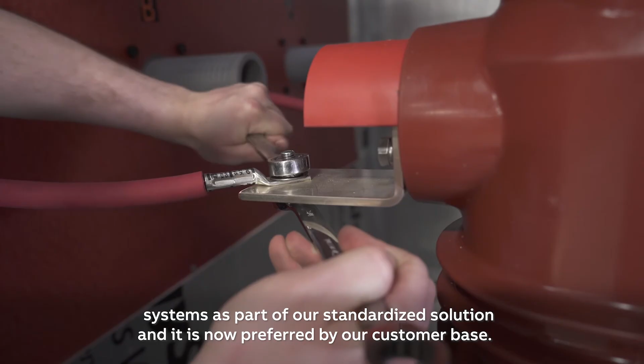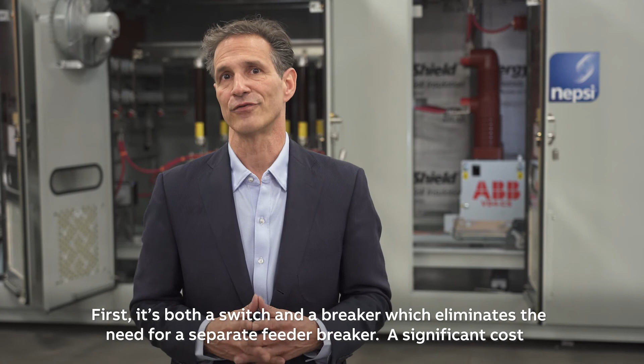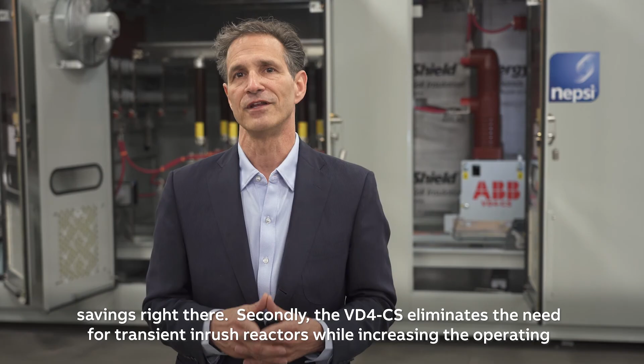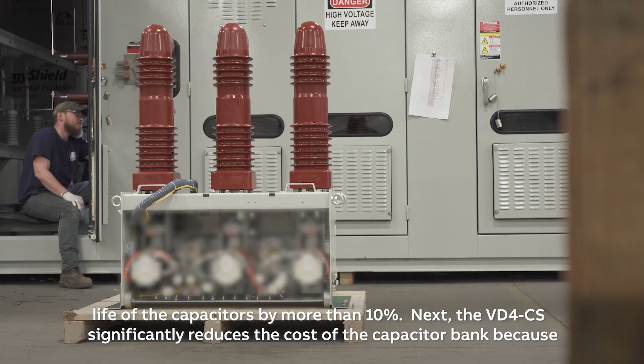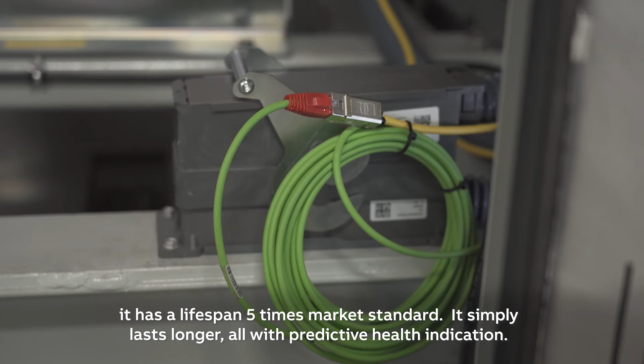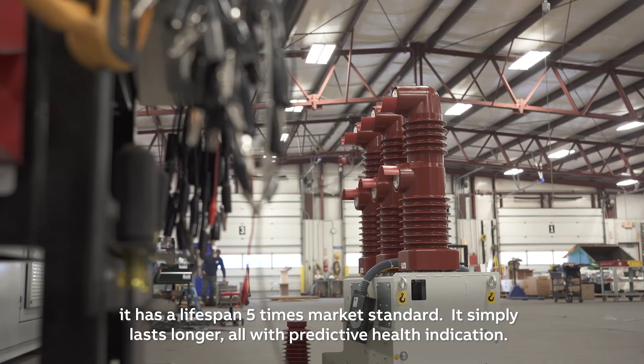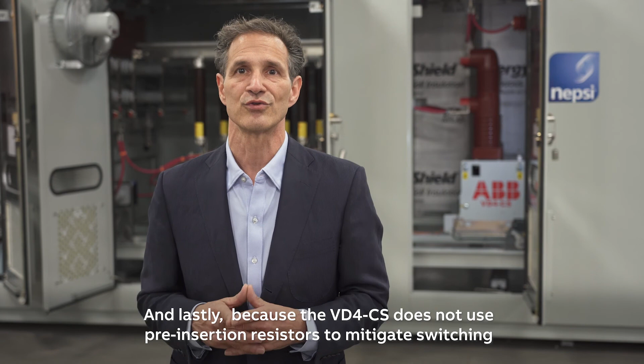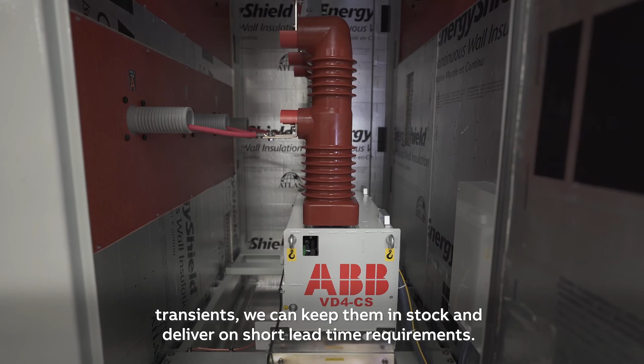What do we like most about the VD4CS? Well, we have quite a long list, but just to mention a few of the highlights. First, it is both a switch and a breaker, which eliminates the need for a separate feeder breaker. A significant cost savings right there. Secondly, the VD4CS eliminates the need for transient inrush reactors while increasing the operating life of the capacitors by more than 10%. Next, the VD4CS significantly reduces the cost of the capacitor bank because it has a lifespan 5 times market standard. It simply lasts longer, all with predictive health indication. And lastly, because the VD4CS does not use pre-insertion resistors to mitigate switching transients, we can keep them in stock and deliver on short lead time requirements.